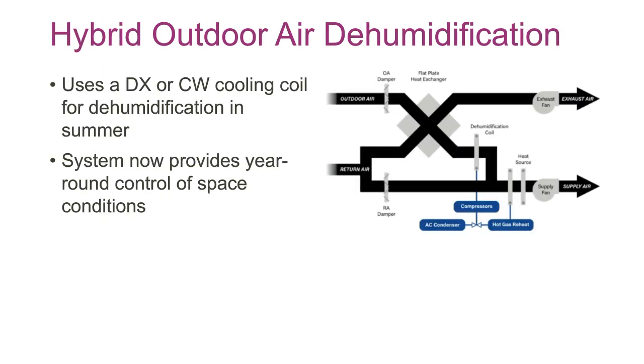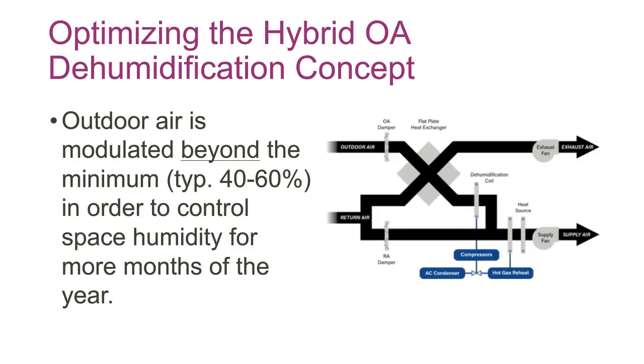There is an answer, however, and this is what we've worked out through the years to using the outside air, but not going all the way to 100%, and also adding a cooling coil to handle the summer dehumidification so that you have a year-round solution. And that solution uses a chilled water coil within the system, and now you can control year-round. And I'll go into a few details in a sec. And so kind of optimizing that hybrid concept, you would modulate the outside air from the IAQ minimum up to typically around 40 to 60% of the supply air, not 100%, to control the humidity for more months during the year.